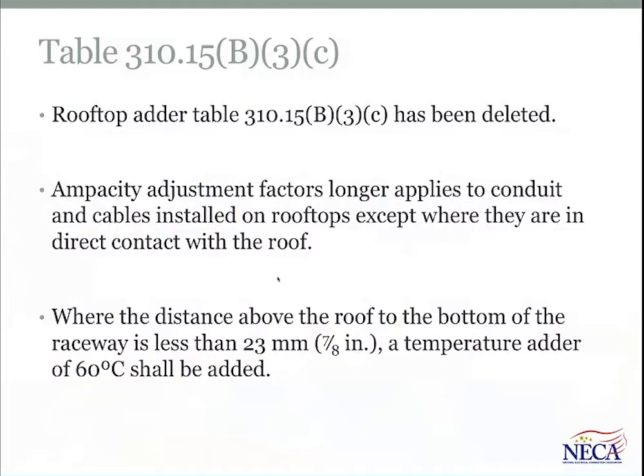Another significant change in the NEC in Article 310 is the deletion of Table 310.15(B)(3)(c). That's the rooftop adder, the rooftop correction factor adder table. That table has been deleted. We no longer are required to take a correction factor for installations of cables and conduits installed on roofs, except where they're in direct contact with the roof.